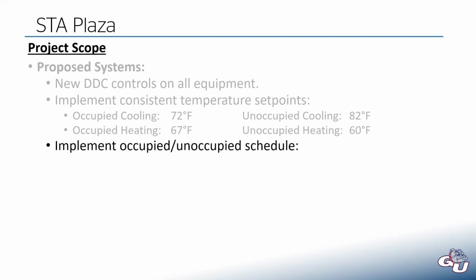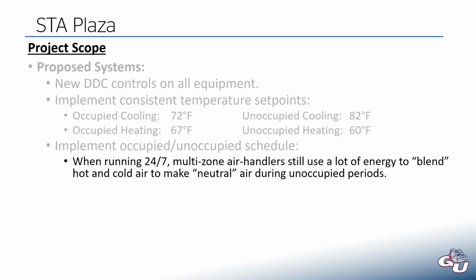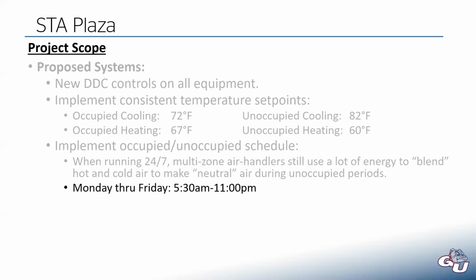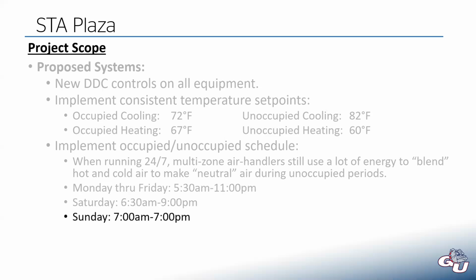We also implemented an occupied, unoccupied schedule. So remember, with these multi-zone units, specifically constant volume multi-zone units, when those are running 24/7, they are still using a ton of energy to blend that hot and cold air to make neutral air. When we're in those unoccupied periods, we probably don't need a lot of heating or cooling, but if the units are running, they're just providing neutral air. But to achieve that, with this type of system, they're taking cold air and hot air, spending energy to condition both of those, mixing them together to get plain neutral air. So it still takes a ton of energy. So instead, we're going to implement this schedule: 5:30 to 11, Monday through Friday, 6:30 to 9 on Saturday, 7 to 7 on Sunday, because that is when the plaza is actually open.